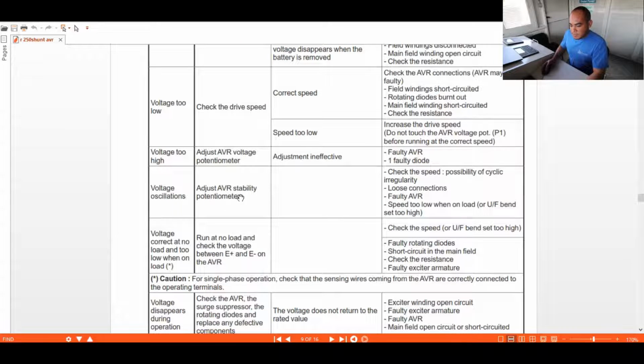So next, if the voltage is too high, just adjust the voltage potentiometer. Adjusting it can also affect your AVR. Okay, so either your diode or the AVR itself is faulty. This is the thing you have to check. If it is over voltage, check if your AVR is faulty, or check if the diode is short circuit, or if it is open, or what else can affect this voltage and why it is too high.